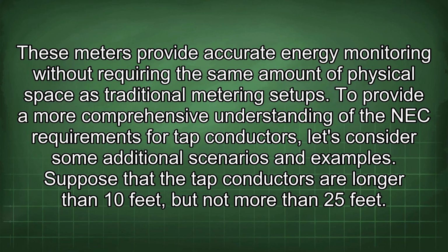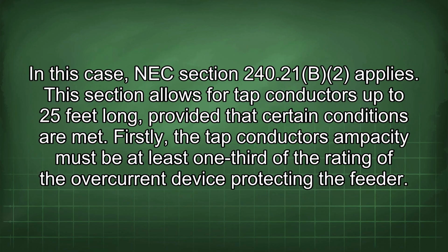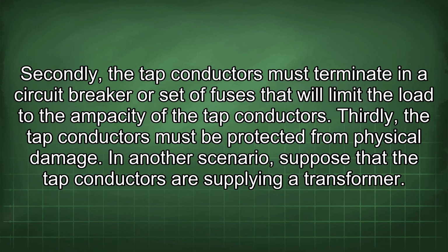To provide a more comprehensive understanding of the NEC requirements for tap conductors, let's consider some additional scenarios and examples. Suppose that the tap conductors are longer than 10 feet, but not more than 25 feet. In this case, NEC section 240.21(B)(2) applies. This section allows for tap conductors up to 25 feet long, provided that certain conditions are met. Firstly, the tap conductor's ampacity must be at least 1/3 of the rating of the overcurrent device protecting the feeder. Secondly, the tap conductors must terminate in a circuit breaker or set of fuses that will limit the load to the ampacity of the tap conductors. Thirdly, the tap conductors must be protected from physical damage.